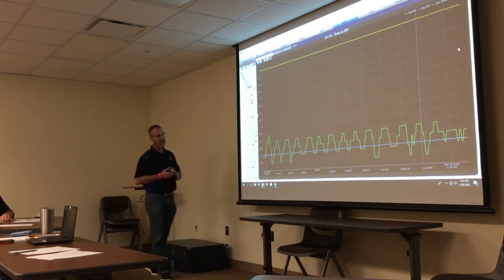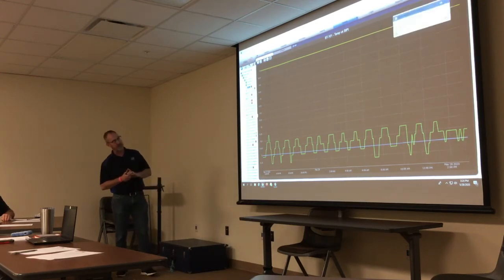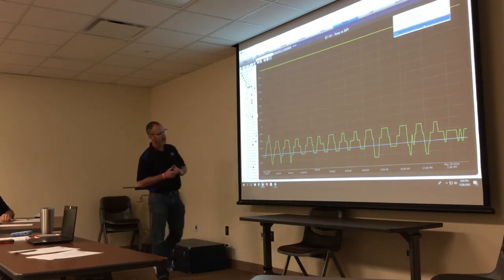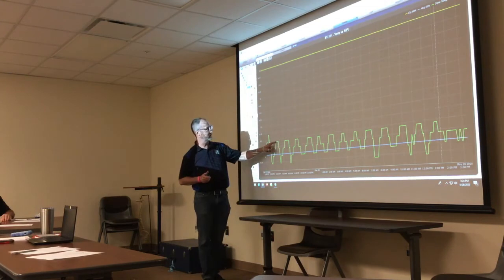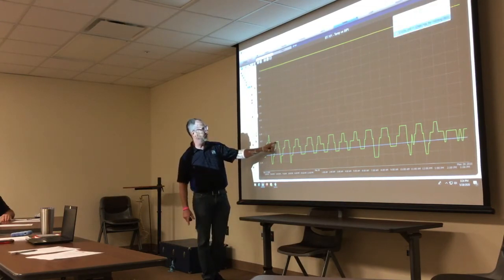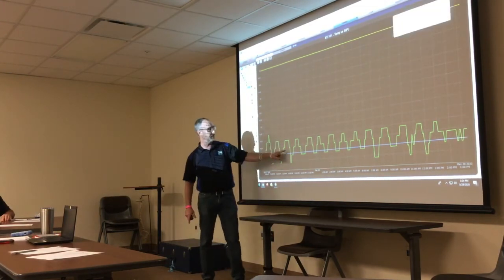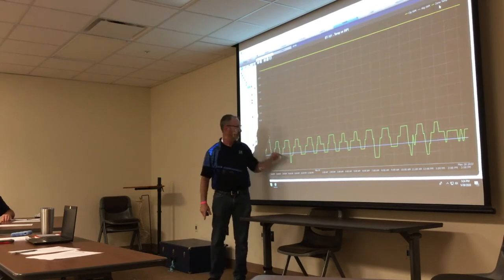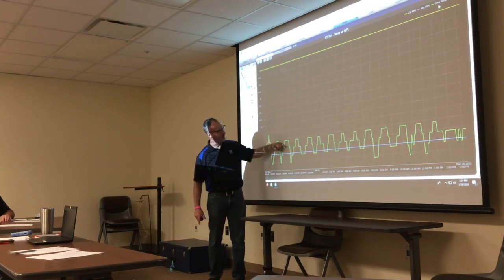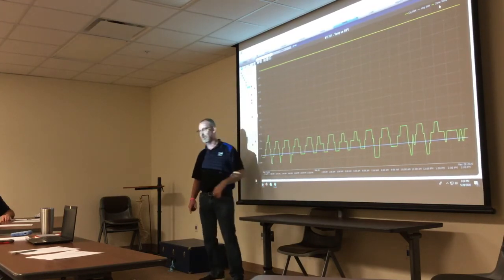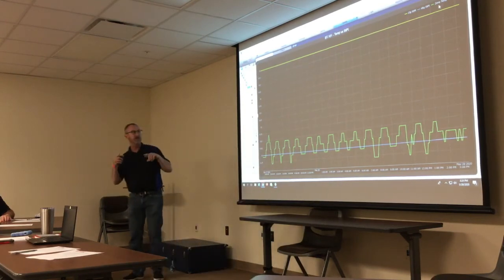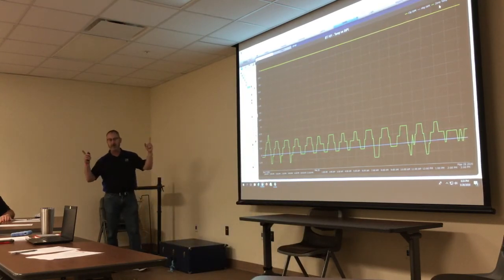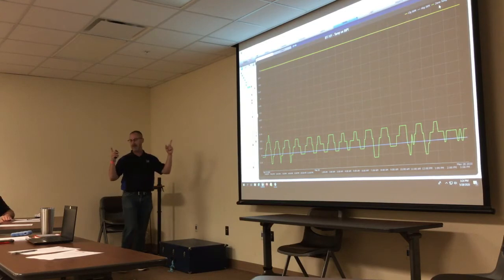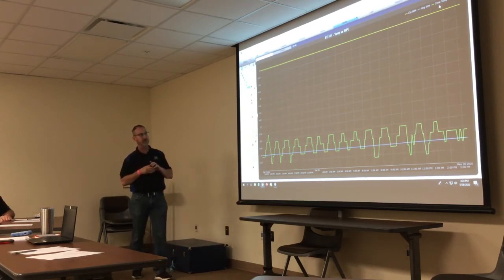That checkbox that says display gaps in trend data - what that means is that for some reason my zone temperature stopped reading here, and I didn't get it back until here. What it'll do is draw a straight line at an angle down to the next point, so it lets you see visually that there was a loss of communication or a gap in the trends.